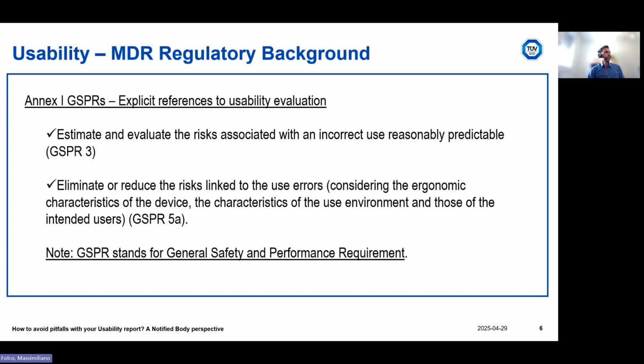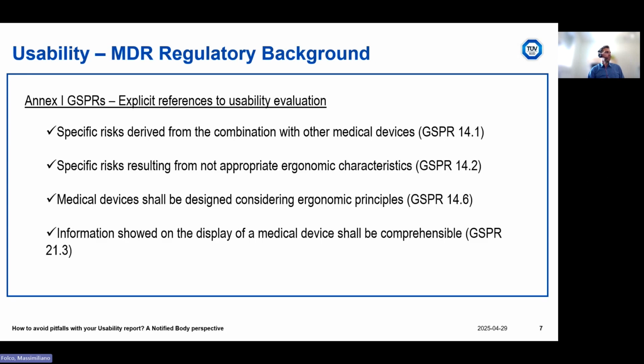Here, for example, we have GSPR, where GSPR stands for General Safety and Performance Requirements, that are listed in Annex 1 of MDR. For example, GSPR 5 requires to eliminate or reduce the risks linked to the use errors, very important, considering the characteristics of the device, of the user environment, and of the intended users. Then, for example, we have other GSPRs that are requiring to consider risks deriving from the combination with other medical devices, are requiring to design information, for example, labeling, that have to be comprehensible to the users. And this is a usability aspect, of course, the fact that it has to be comprehensible.